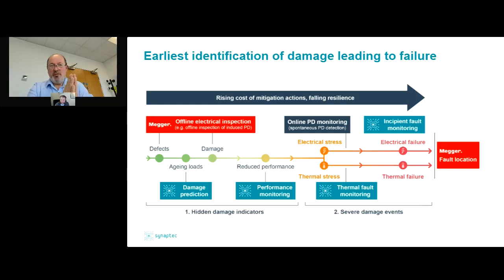But then there can often be an enormous period of time here. In fact, I was with a very large customer today on their site who are taking their cable offline and testing using all the correct best practices, and PD and Tan Delta or VLF, all the Megger equipment is being used. But the period between tests by agreement with the regulator is 3 years. Now, in those 3 years, an awful lot of things can go wrong. An awful lot of problems can occur. And indeed, this customer has a significant problem with water ingress. The joint bays are flooding very gradually over time, and that could happen within a matter of weeks or a month. 3 years is just an awfully long time between testing.